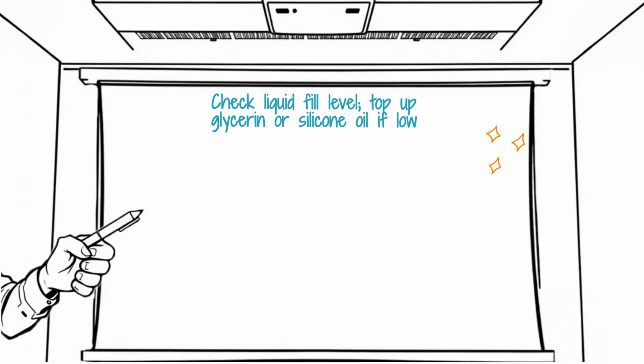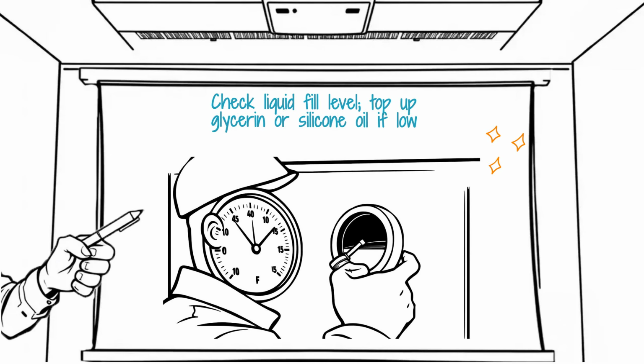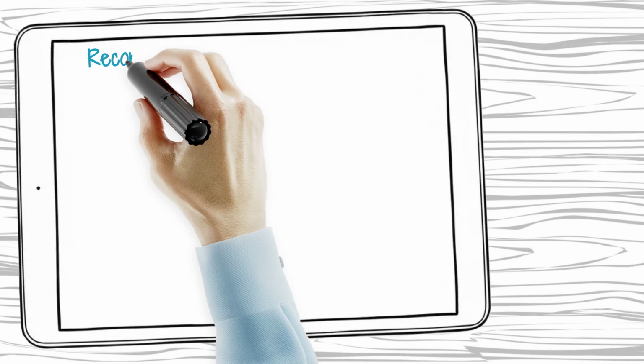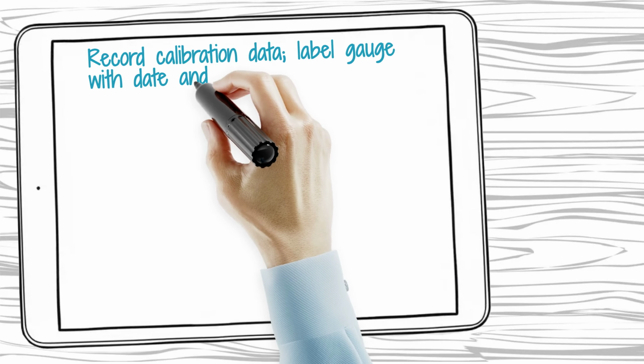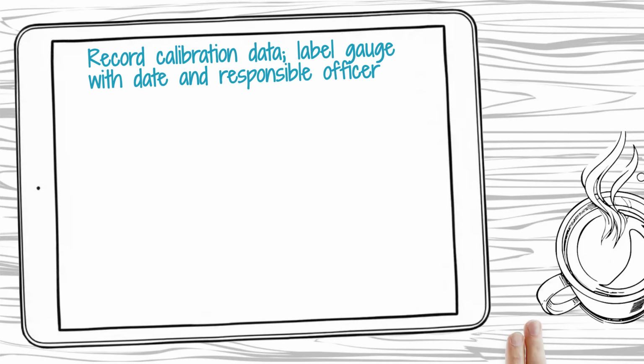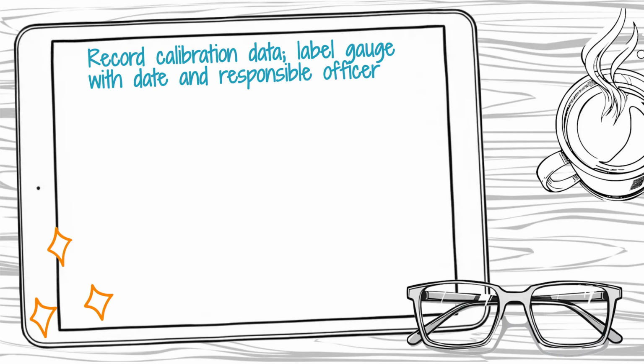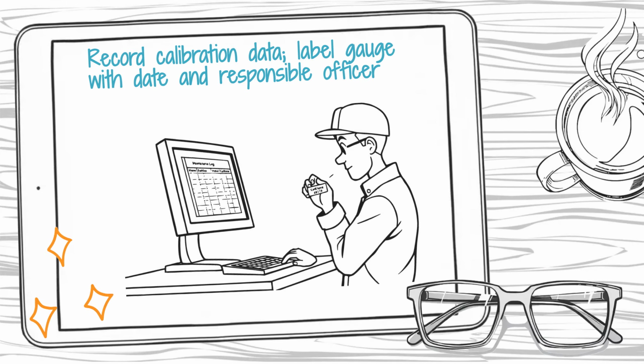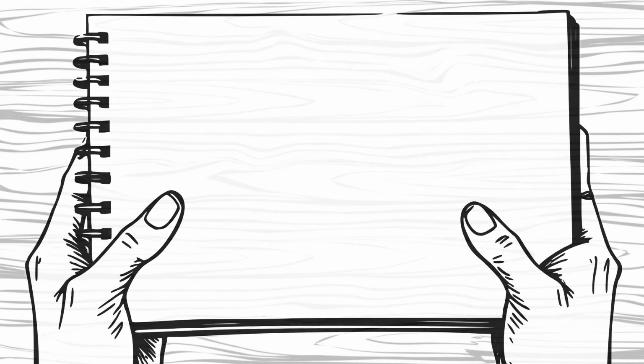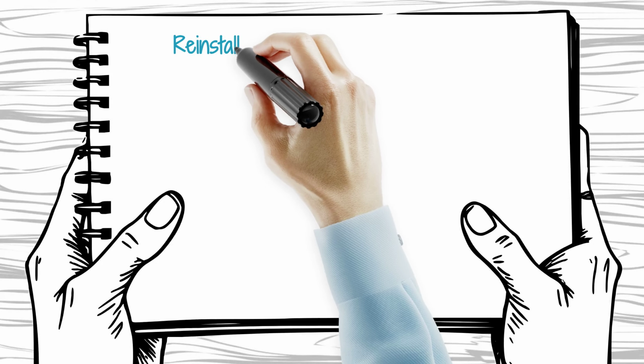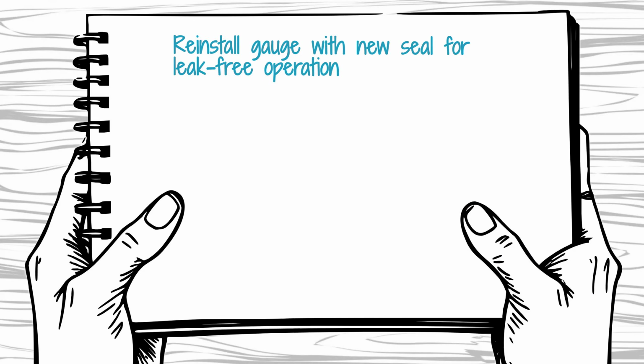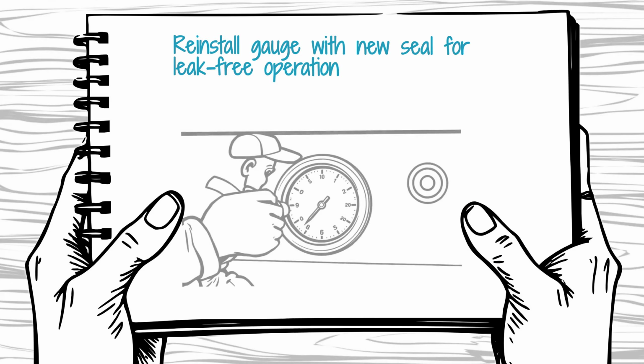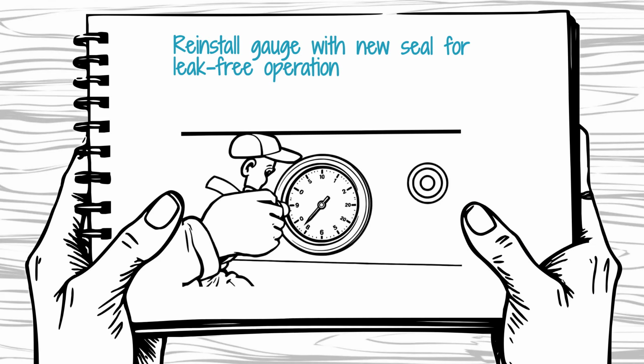Once the adjustments are complete, perform a final sweep from zero to maximum and back down to zero to check for hysteresis. Always record the final calibration results in the vessel's planned maintenance system and apply a calibration sticker to the gauge face with the date and the name of the officer responsible. Reinstall the gauge using new thread sealant or a copper washer to ensure a leak-free connection. Regular calibration ensures that your engine room readings are trustworthy and that your machinery stays protected throughout the voyage.